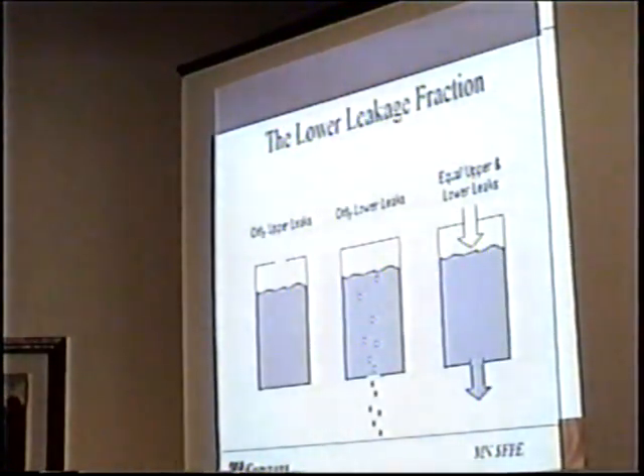So, a quick schematic, just to stimulate the thinking process here. If we have a leak only on the top of the enclosure, and we have, once again, no diffusion of gases, very important, or it would diffuse upwards and flow over through that crack, but essentially the hold time is infinitely long at this point in time. Now if it's on the bottom, if this was water, we'd see this kind of gurgling effect. But the mathematics don't care, they don't see that. So if it's all on the bottom of the room, once again, infinitely long hold time.